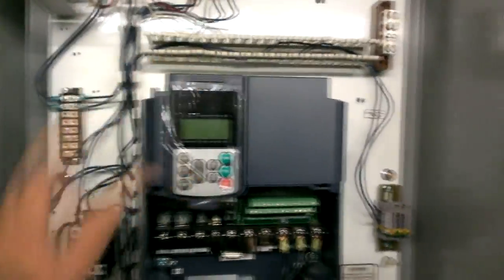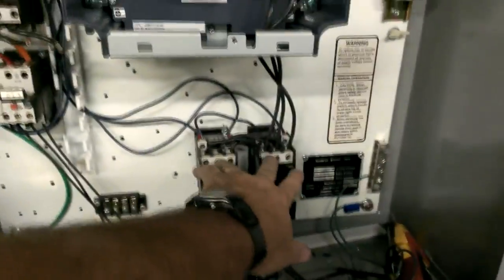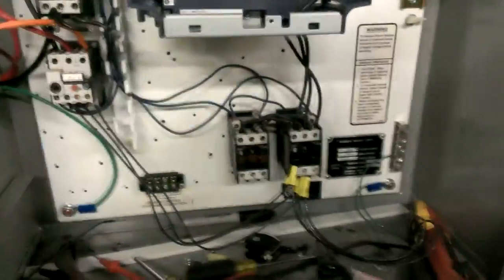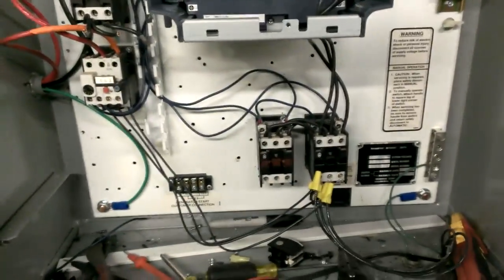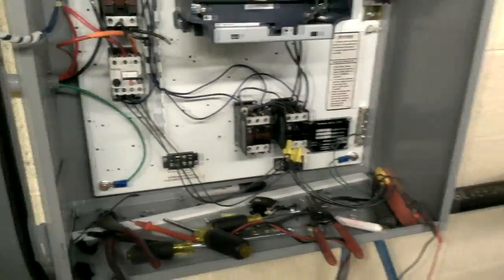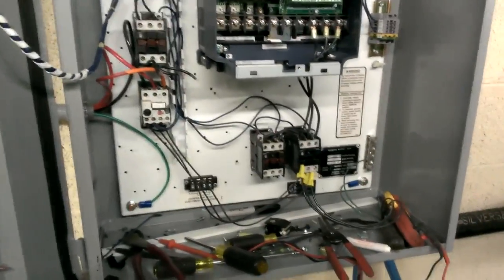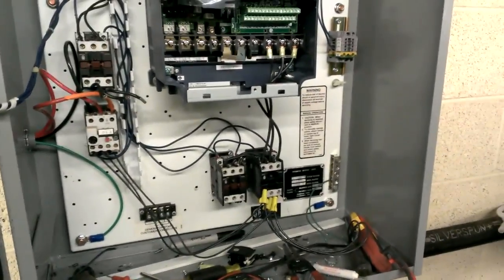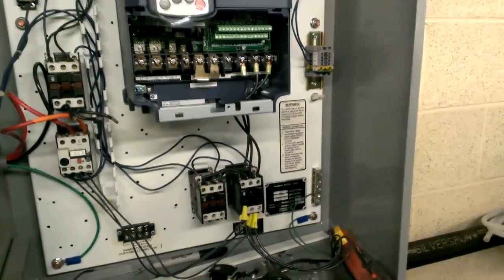So I got my VFD here that we bought, reused a couple contactors. This is going to be tricky, but basically an output of the VFD is going to go through one of those at a time. That way we can switch to a backup pump when one fails.